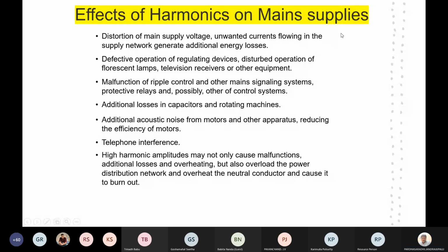There is defective operation of regulating devices, disturbed operation of fluorescent lamps, television receivers or other equipment, and malfunction of ripple control and other mains signaling systems, protective relays, and possibly other control systems. You can find additional losses in capacitors and rotating machines, acoustic noise from motors and other apparatus, reducing the efficiency of motors. You can also find telephone interference. High harmonic amplitudes may not only cause malfunctions, additional losses and overheating, but also overload the power distribution network and overheat the neutral conductor and cause it to burn out. So these are the various effects of harmonics on the supply.